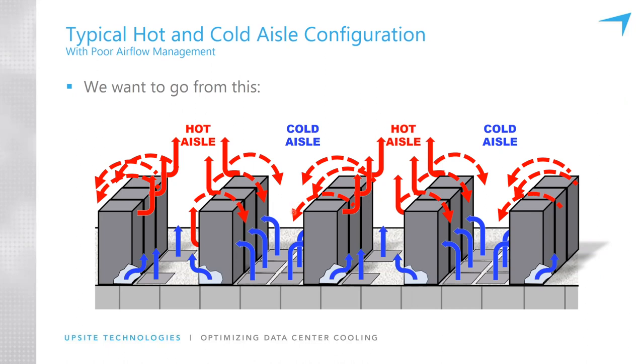Hot air can flow over the tops of cabinets, and a lot of this is invisible and addressed by having too much cold air, or over-delivering cold air to the cold aisle, to try and abate some of these problems. So just because there are no hotspots in the data center doesn't mean that some of these poor airflow conditions aren't occurring. Poor airflow management, the lack of containment, can be overcome in a number of cases by having a lot of air and a lot of cold air thrown at the problem, but it's a very inefficient way to do it.